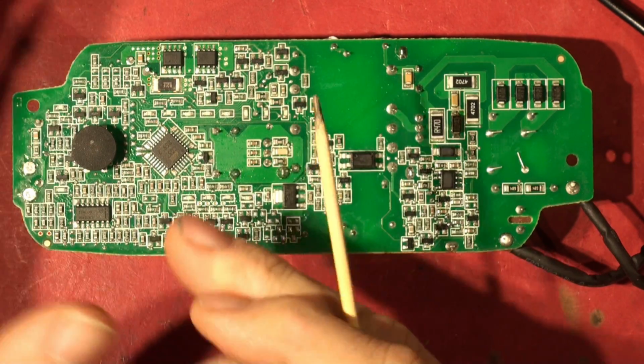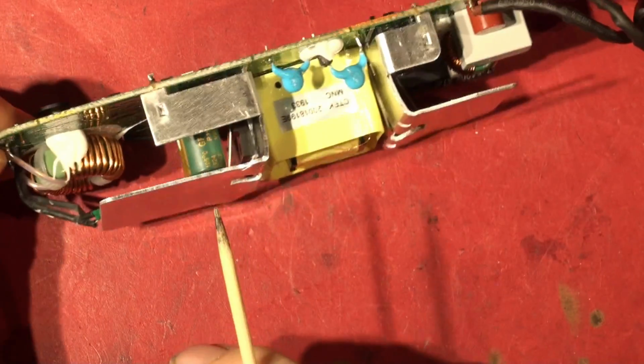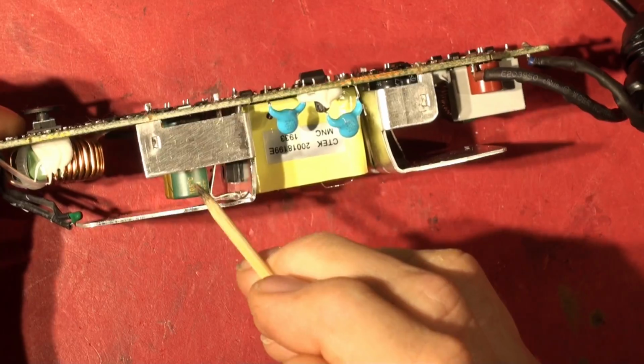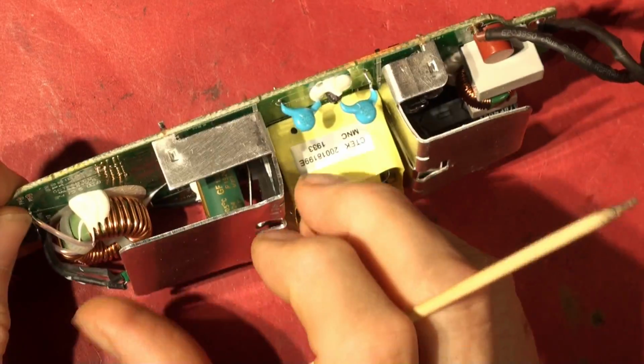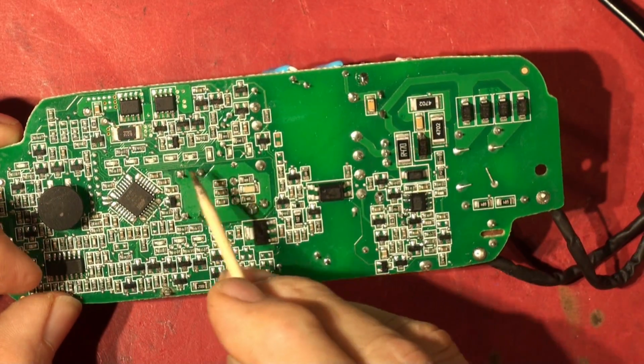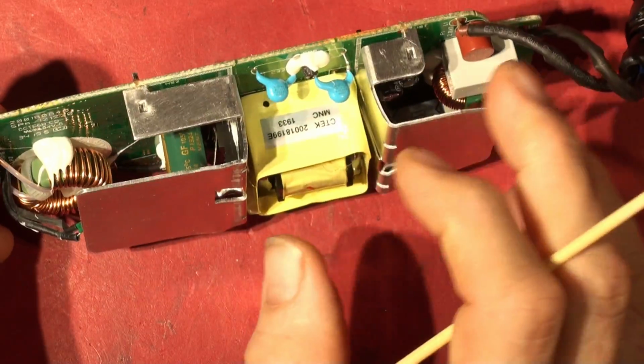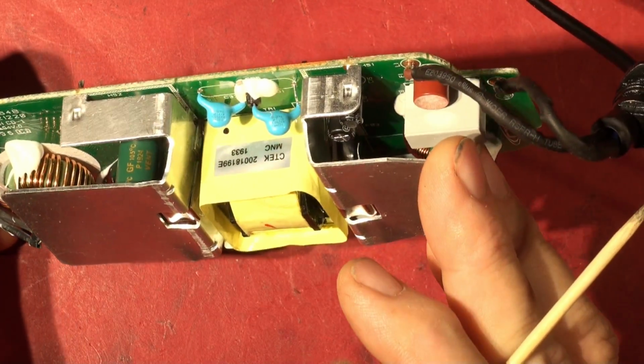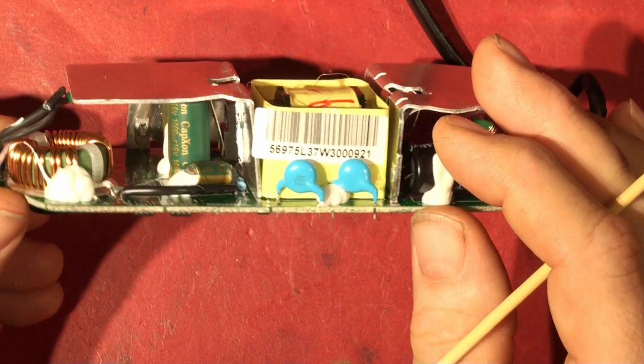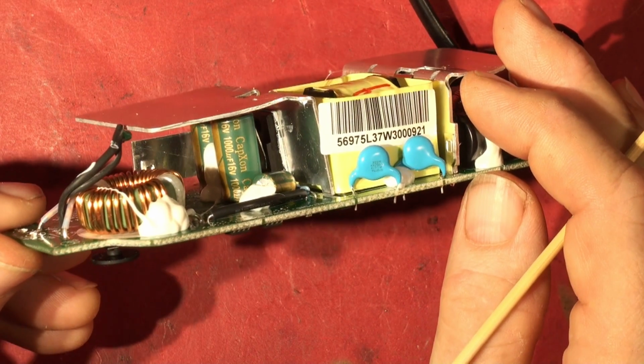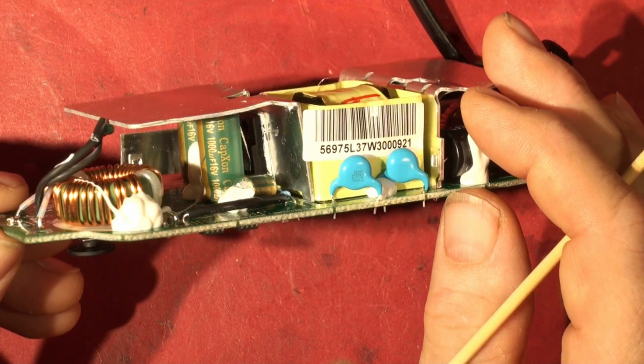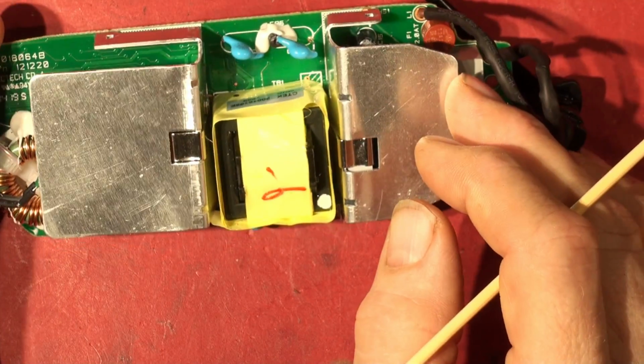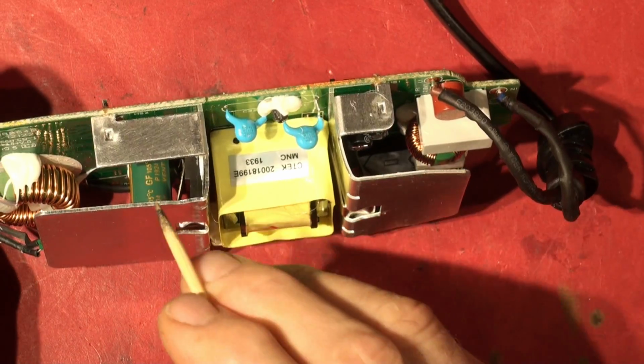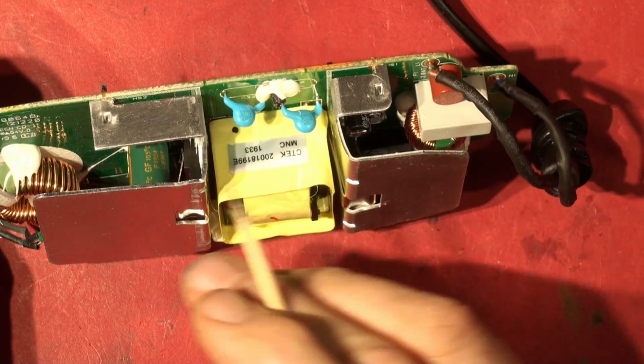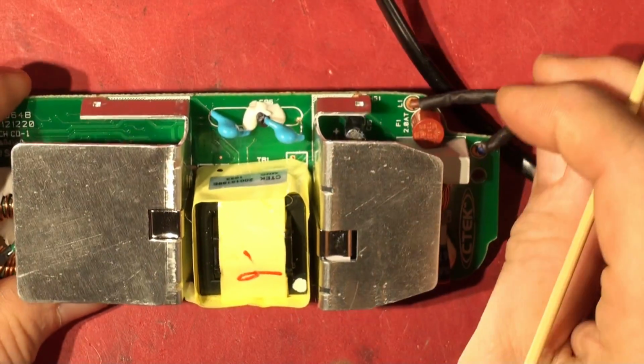Clearly this micro needs to know what's going on. You've got the secondary of the transformer here, there's a smoothing capacitor, 2 smoothing capacitors in parallel, and they are 105-degree ones, vented ones, which is good. CapXon, never heard of them. 1000 microfarad, 16 volt, okay. I would like to have seen 20 volts in there, because this is going to be working up to 15.5. That's pretty close to the wire, but never mind.